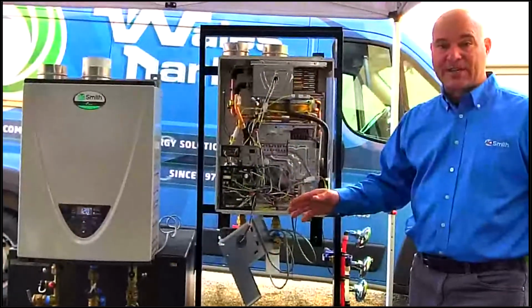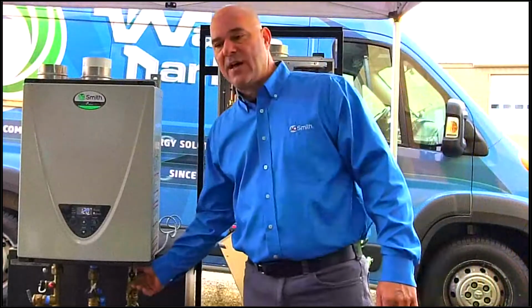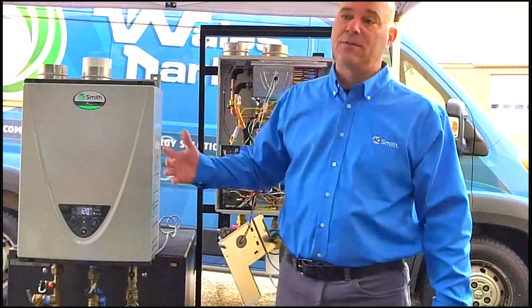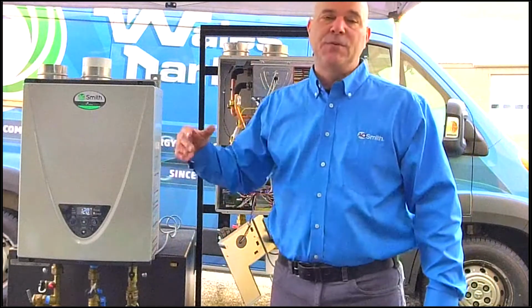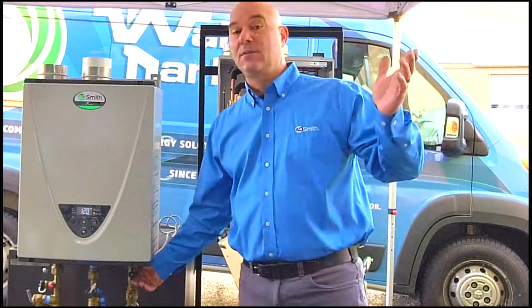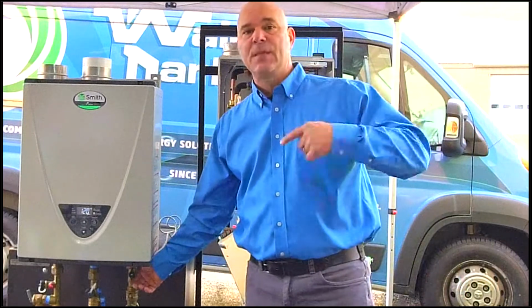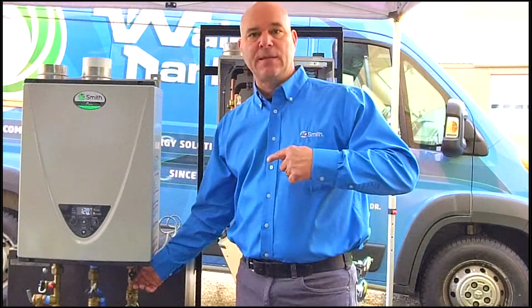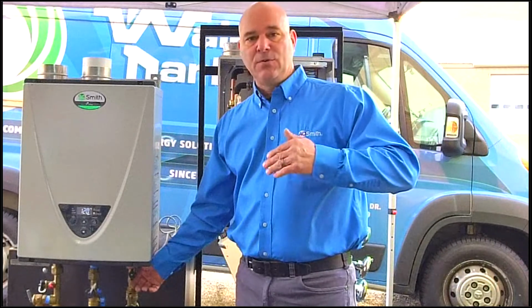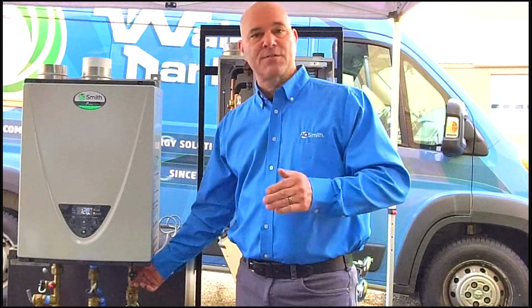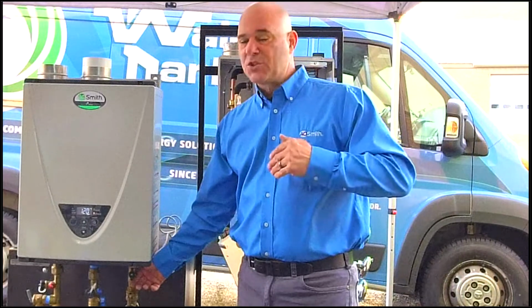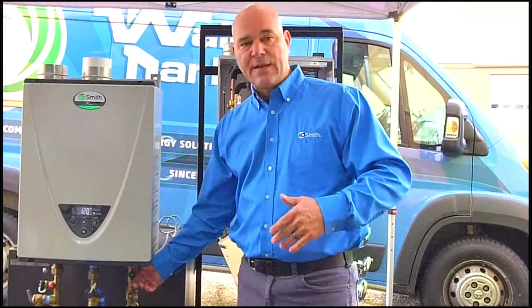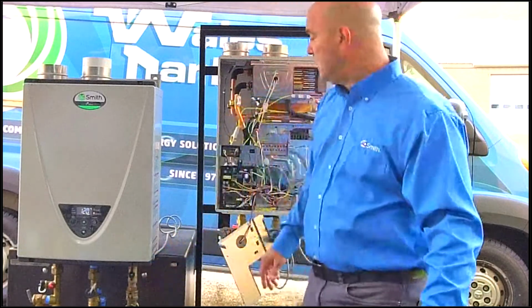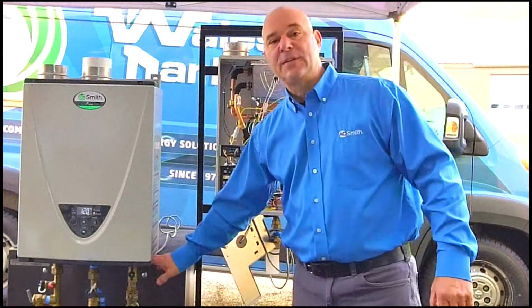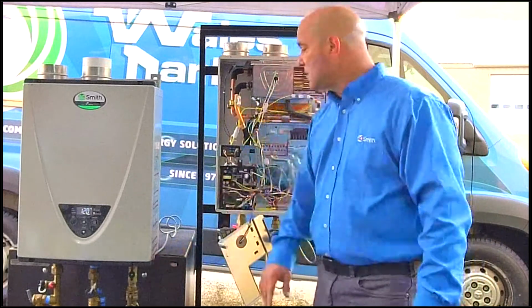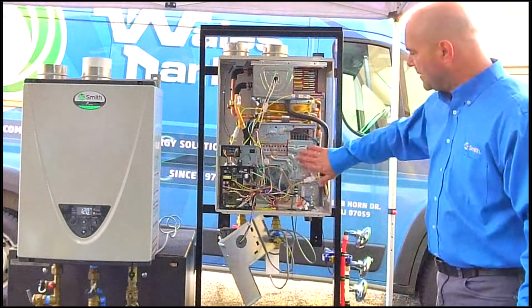If you're going to do a pressure check on the unit, you have to make sure that the gas valve is off. There are 5 solenoids on the back side of the gas valve. If you do not shut the gas pressure off and you pressurize to 5 psi or whatever number you use, it will blow the O-rings out of the gas valve. Our contractor services group is on jobs constantly, and we're sharing what we have seen in the field. If a guy forgets to close this valve, it's a problem. If a guy doesn't back this gas valve up when he tightens it, it's a problem. So just be aware. So this right here is the gas valve.